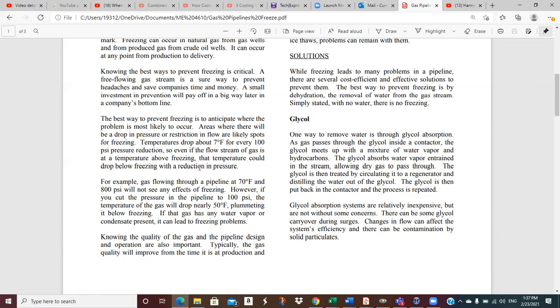For example, gas flowing through a pipeline at 70 degrees Fahrenheit and 800 PSI will not see any effects of freezing. Well, I believe that. That's pretty common sense. However, if you cut the pressure in the pipeline to 100 PSI, the temperature of the gas will drop nearly 50 degrees F, plummeting it below freezing. So it was a combination.